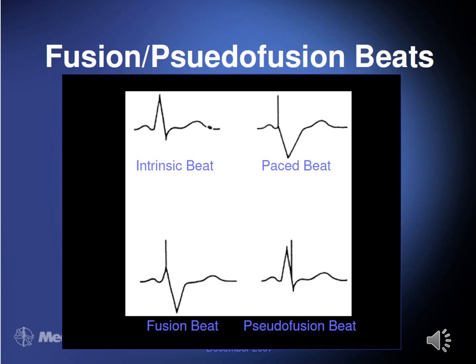Okay, so looking at fusion and pseudofusion beats, basically what this is, when the pacemaker is doing what it needs to, it first senses and says, oh, I need to produce a paced beat. Then it produces that paced beat. What happens is that fusion beat is happening in that time frame between when the pacemaker realizes it has to do something and does something. So you can see it's pretty close to around the QRS. It is not in the vulnerable area that can set the patient into arrhythmias on the T wave.